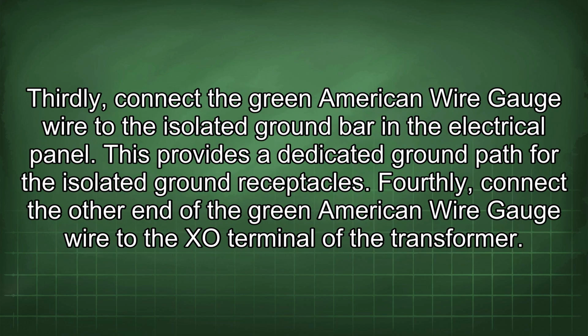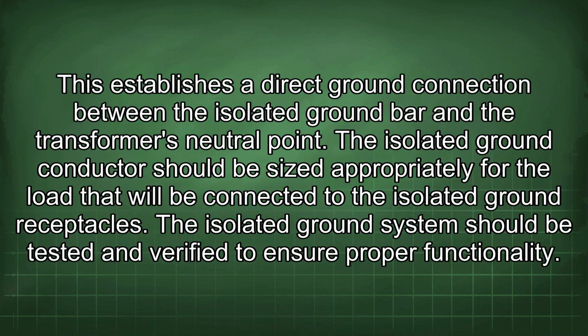Thirdly, connect the green American wire gauge wire to the isolated ground bar in the electrical panel. This provides a dedicated ground path for the isolated ground receptacles. Fourthly, connect the other end of the green American wire gauge wire to the X0 terminal of the transformer. This establishes a direct ground connection between the isolated ground bar and the transformer's neutral point.